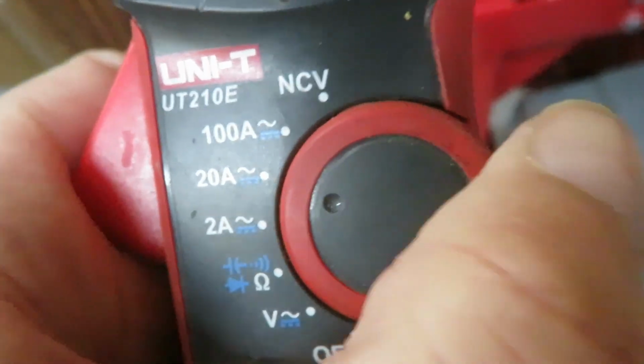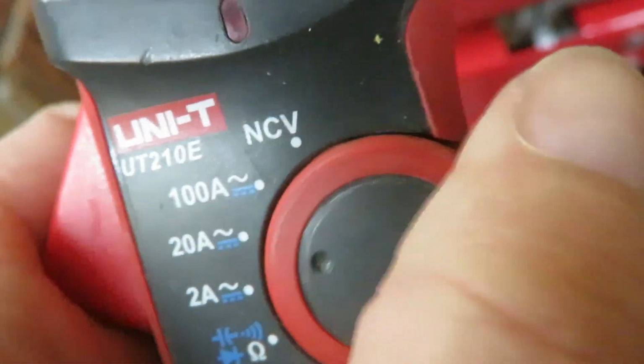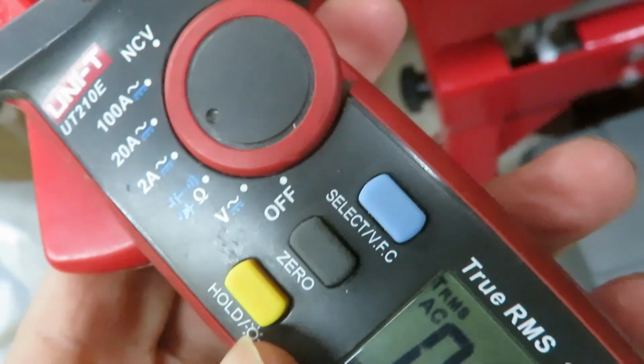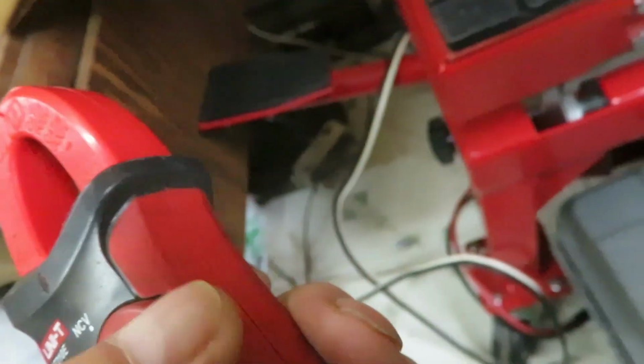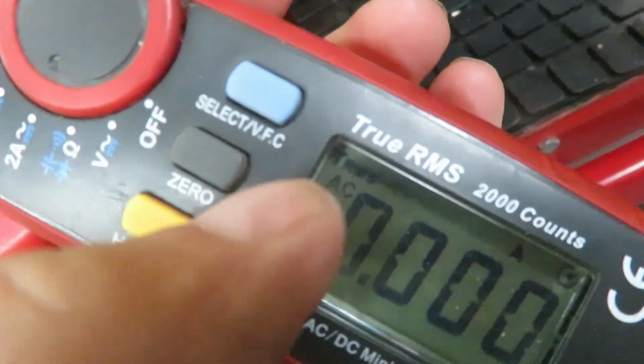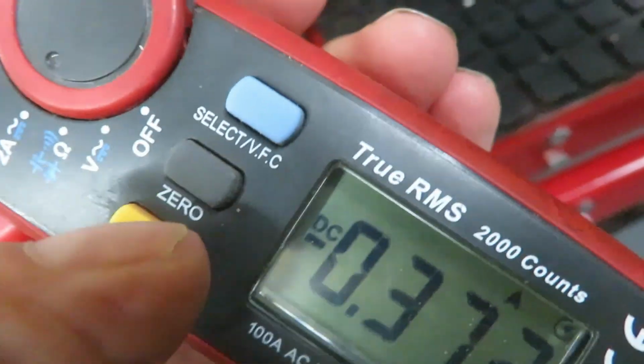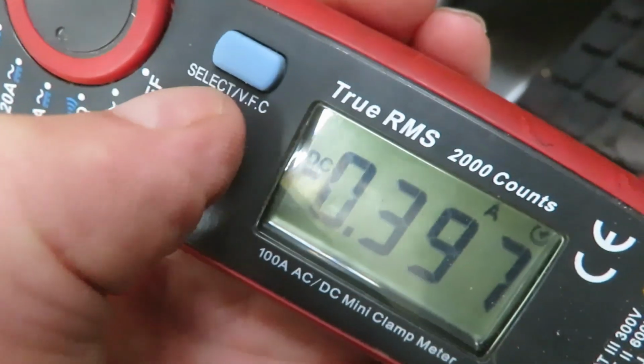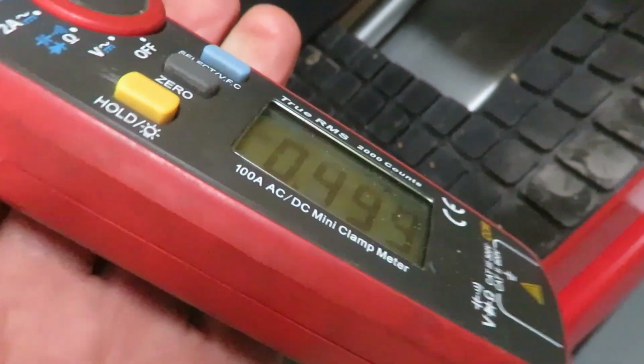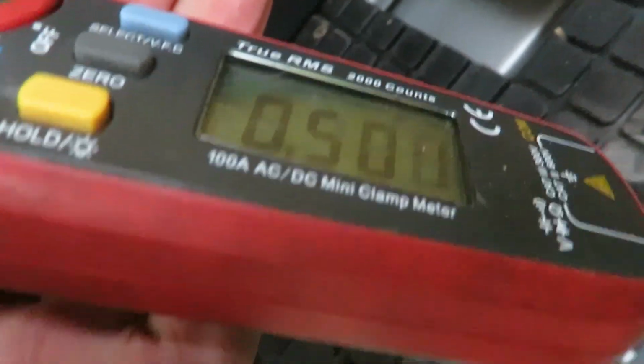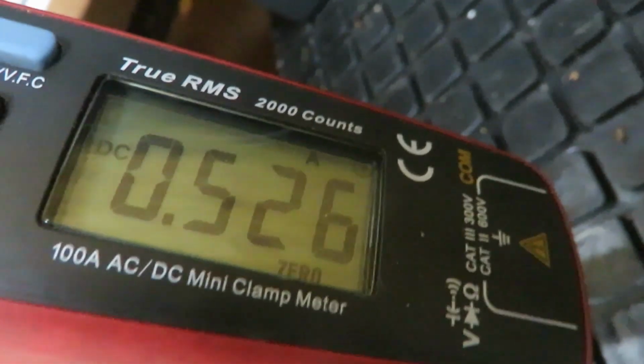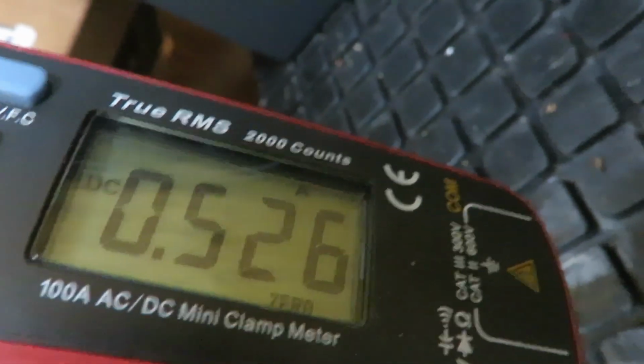You could probably get better resolution if I go to this other scale - the 20 amp range, then down to the 2 amp scale for good resolution. Then of course we've got to go back and select DC again, and zero it out. Pretty close - let's put this on here. Yeah, so it's taking about half an amp. The resolution on the higher scale doesn't show it as well, but it's taking 526 milliamps, so over half an amp just to run it.